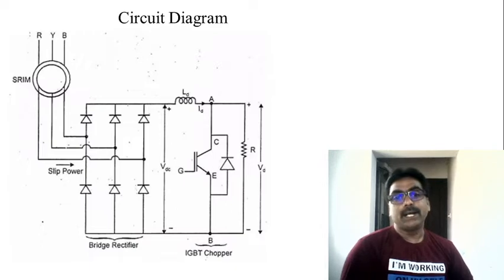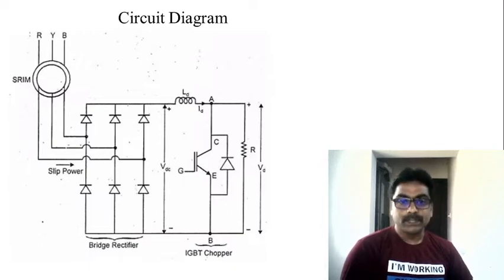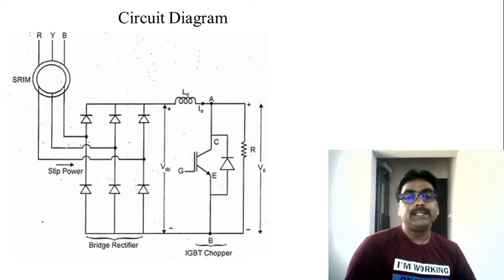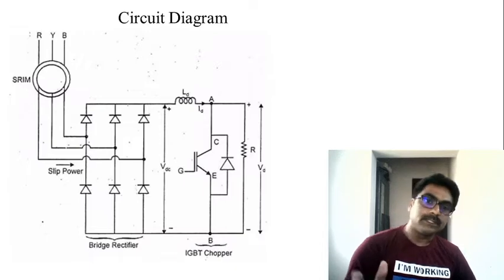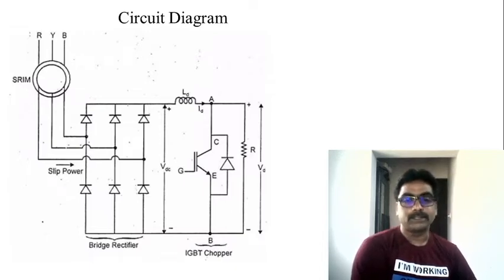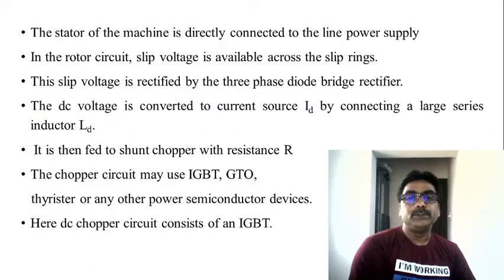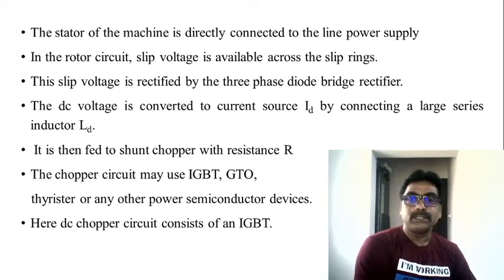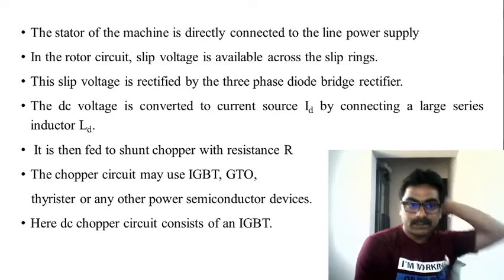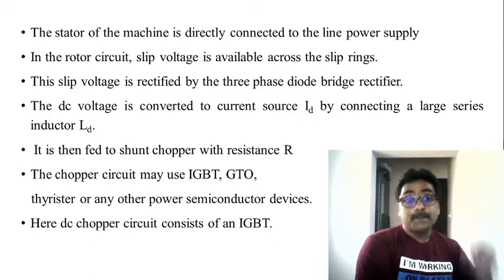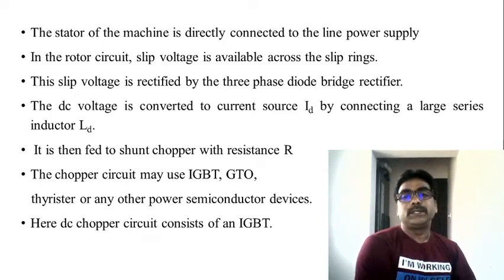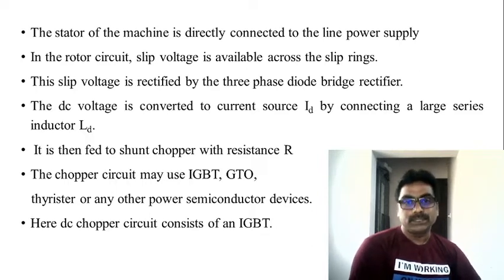There is also a DC link inductor connected in series, and we have a chopper circuit. The external resistor is connected across the switch — it is connected across the rotor of the induction motor through this chopper circuit. The DC voltage is converted into a current source by connecting the large series inductor, and that is the purpose of this inductor connected in series to the circuit.